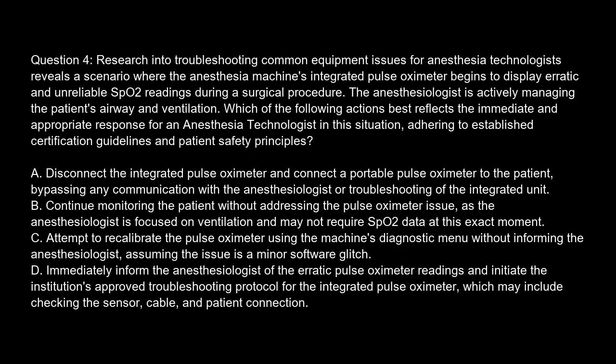Option D. Immediately inform the anesthesiologist of the erratic pulse oximeter readings and initiate the institution's approved troubleshooting protocol for the integrated pulse oximeter, which may include checking the sensor, cable, and patient connection.